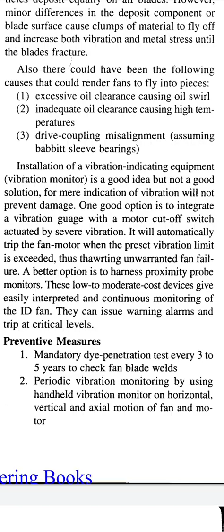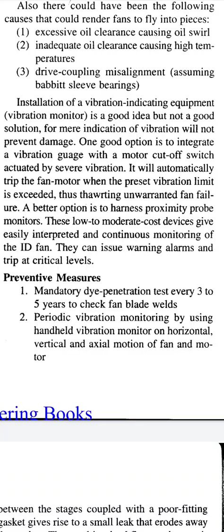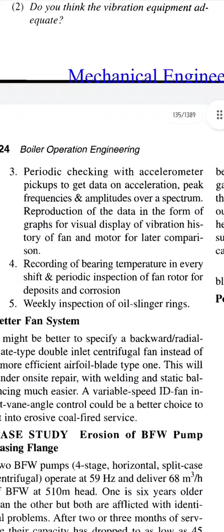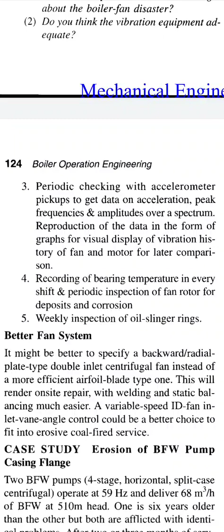Preventive measures: mandatory dye penetration test every 3 to 5 years to check fan blade welds. Periodic vibration monitoring by using a hand-held vibration monitor on the horizontal, vertical and axial motion of fan and motor. Periodic checking with accelerometer pickups to get data on acceleration, peak frequencies and amplitudes over a spectrum. Reproduction of the data in the form of graphs for visual display of the vibration history of fan and motor for later comparison.